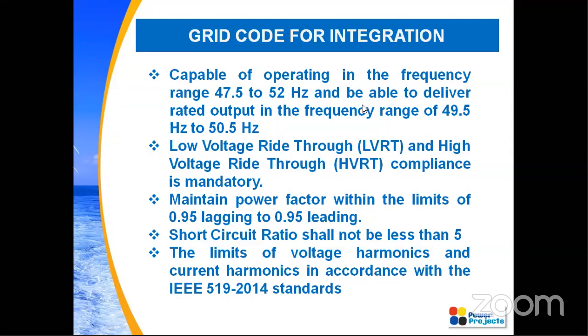Our grid should be capable of operating in the frequency of 47.5 hertz to 52 hertz. Your generating unit should be able to operate, that is, it should be able to generate in the frequency range of 47.5 to 52 hertz, but it should be able to deliver its output in the frequency range of 49.5 hertz to 50.5 hertz. This is the generating frequency, and that is the delivering frequency. This particular condition is also subject to a condition, which I will tell in detail in the upcoming slides.